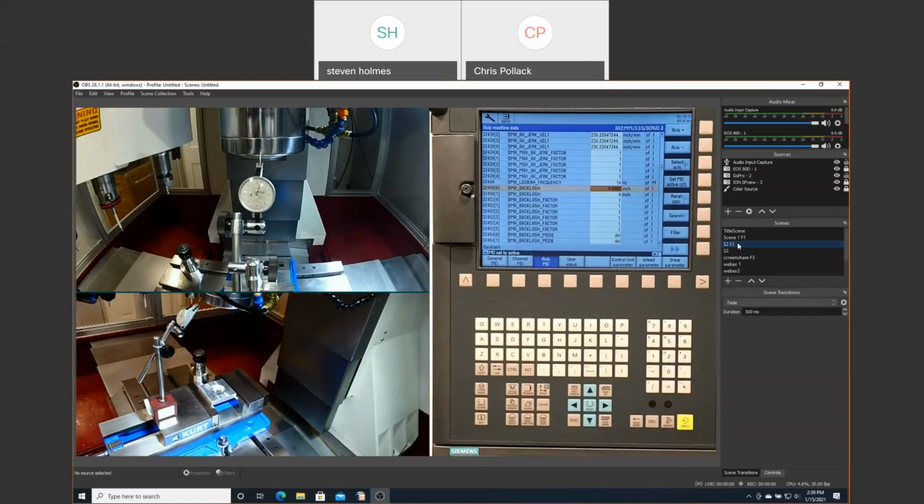Now, if we were to rerun the circular test, which we will do later, we will still see a little spike there because we're looking at the motor encoder. But what we'll see is a 2/10 spike. And that's a needed spike at the motor because it does have to do a reversal. But that big spike is going to come down quite a bit.